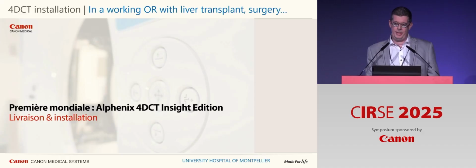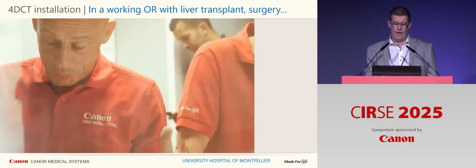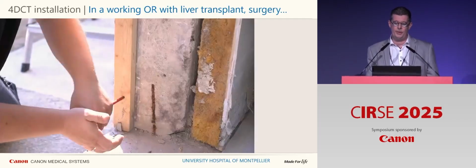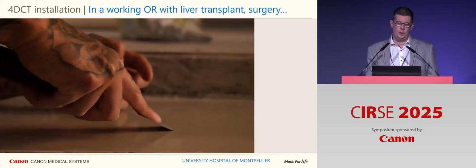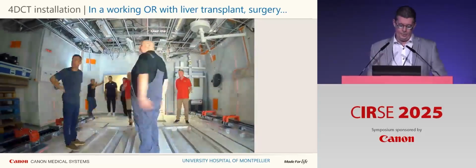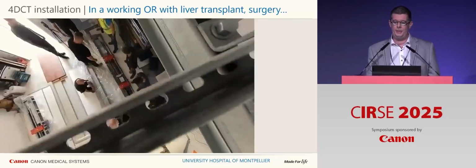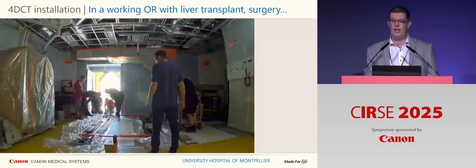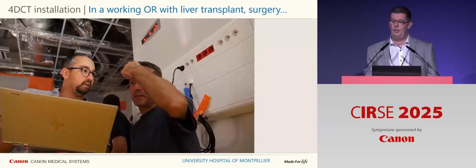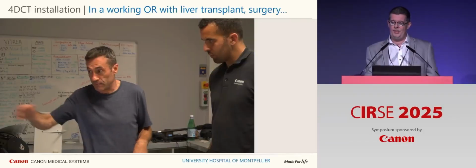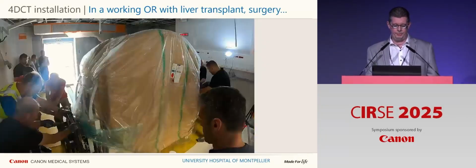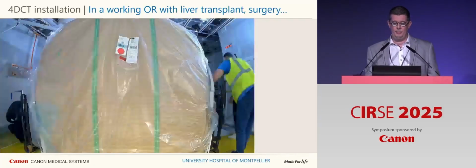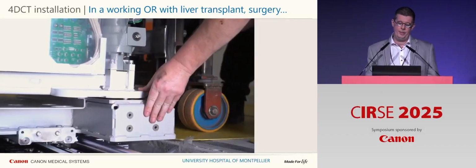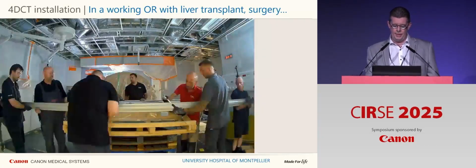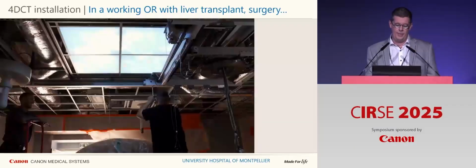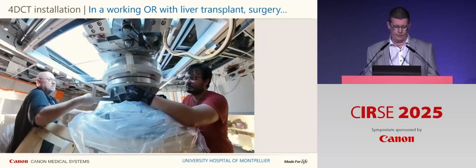You have here a video showing the teamwork and how difficult it is to install such a system in a working operating room without interrupting surgery and liver transplantation next door. For example, the ground rails for the CT gantry had to be built with extreme accuracy because the system must know at all times the exact relative position of the CT, the C-arm, and the table to enable seamless image co-registration across modalities. This was truly a massive work done by Canon's teams, carried out over a 3-month period. And as you can see in this video, heavy access was done through the OR facade to keep activity running during this work.